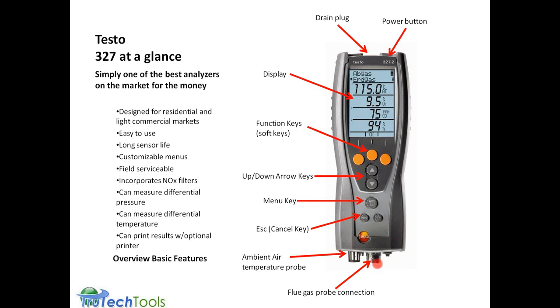The flue gas probe connects the pathway for the flue gases to get inside the meter to be pulled in by the pump and be analyzed. It also has the contacts for the temperature probe for measuring stack temperature, and it also has a pathway to measure draft when you use the draft test mode. Everything is in one single fitting. The fitting is also keyed, so you can only put it in one direction. There's no way of mixing up or confusing the connections.